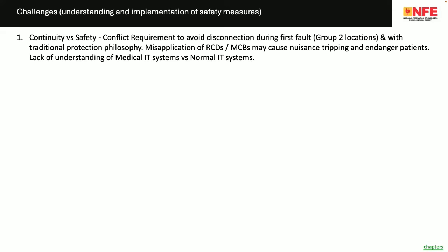For example, if you put RCDs in an inappropriate location, it may trip, which will create a nuisance tripping, which may endanger the patient. Lack of understanding of medical IT system and the normal IT system. Medical IT system is a special safety measure which has to be implemented in the medical location, especially group 2 medical location, and medical IT is required.